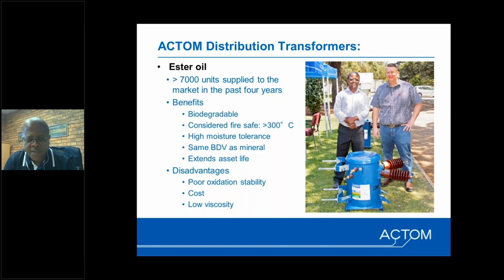The oil is considered fire safe because it's got a fire point of 300 degrees and a flash point of over 350 degrees. The oil is highly moisture tolerant. Mineral oil in moisture saturates at about 20 to 30 ppm, but with esters it's over 200 ppm where it gets saturated. The breakdown voltage for mineral and ester is very similar. It's about 70-75 kV, even up to 80. The esters have an advantage that they extend the asset life. They look after the insulation, and so that is what you need.